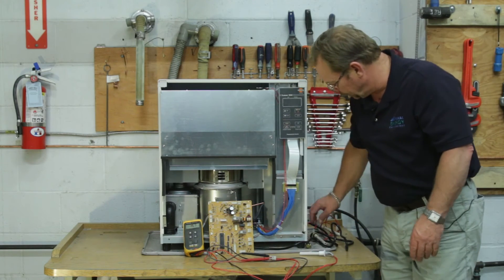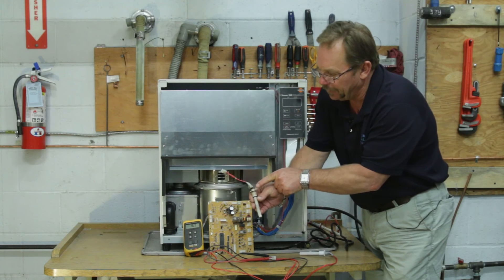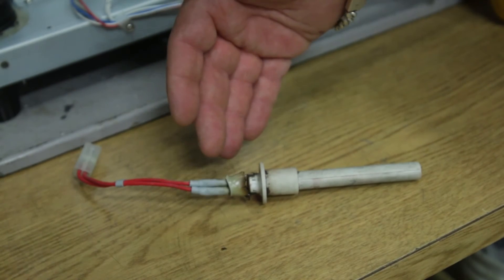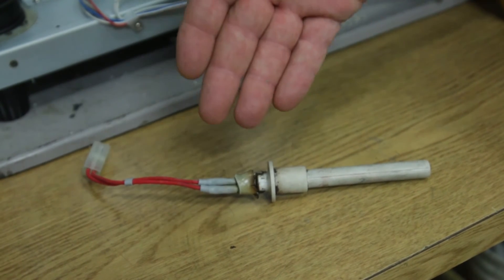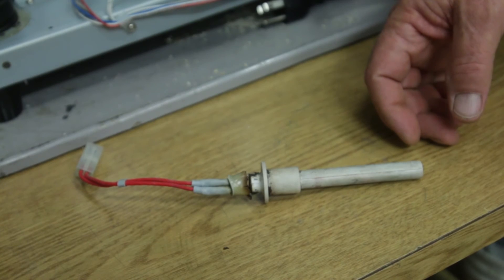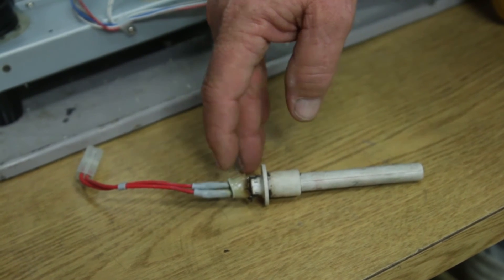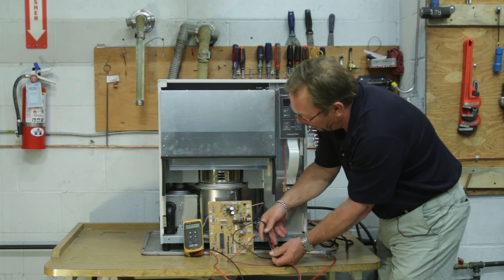We can have other issues going on with igniters, such as this one right here where we have burnt the back side off. What always surprises me about this is even as ugly looking as this igniter is, look at when we take our multimeter and come right on the back side of this, just like we did on the other one, and take that resistance reading.